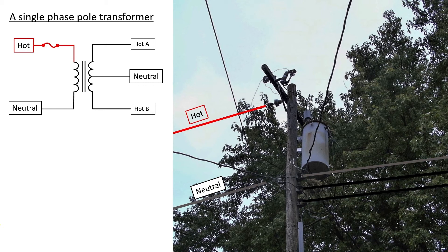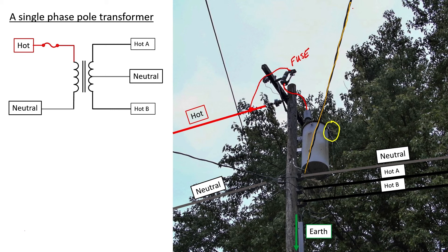The neutral wire is also typically earthed at the pole. Some customers might get their service through underground conduit, so you might also have hots and neutrals going down the side of a pole. The primary side connection to this transformer is made right here — this is a fuse, also called a cutout, and then this hotline leads to the primary bushing of the pole transformer. The neutral connections are on the side. This cable has three wires twisted together — one neutral and two hots — delivering power to customers in overhead and underground connections.